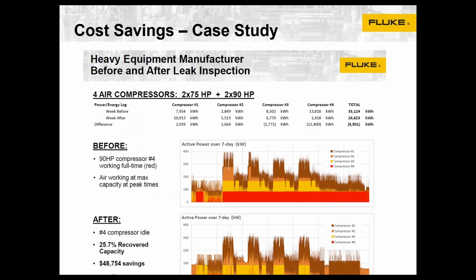So each of the compressors shows energy consumption over time. If you look at how much they're drawing, when they're running, you can get a feel for the different compressors there. Of note, look at compressor number 4. That one, and that may have been their backup as needed compressor, looks like it's running pretty much all the time. After performing the leak inspection activity with the acoustic imagers, and then looking at the after, you can see from this graph down below that backup compressor is hardly used at all.